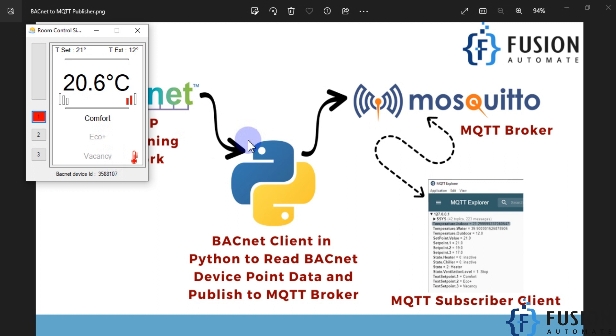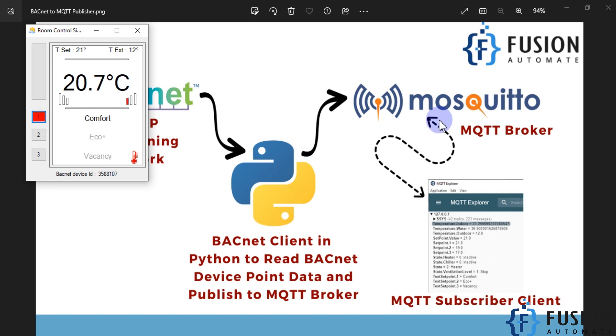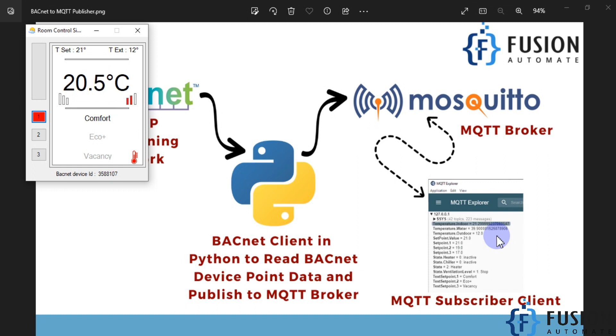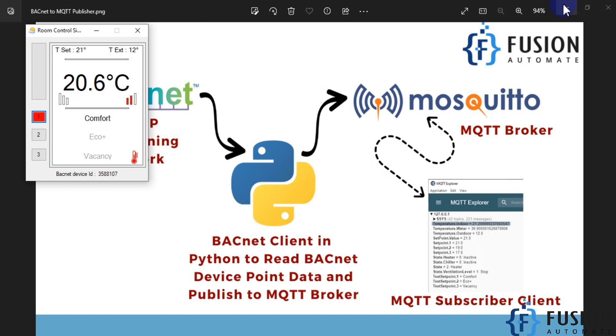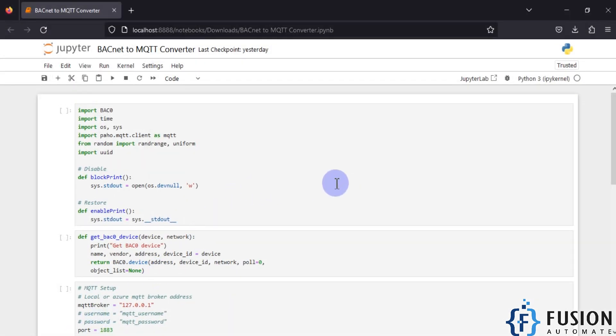Our target is to create a script that can read data from this BACnet device and convert it into MQTT data. It will publish to the Mosquitto broker, and then we create a connection using MQTT Explorer software to read the BACnet device data. The MQTT client software can be anything — your SCADA, MES, PLC, Arduino, or Ignition SCADA — as long as it supports MQTT. So let's minimize this and open our Jupyter Notebook.